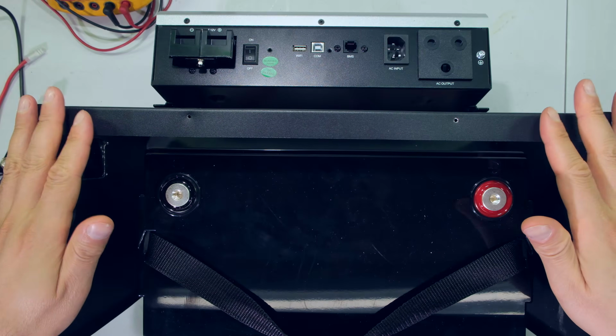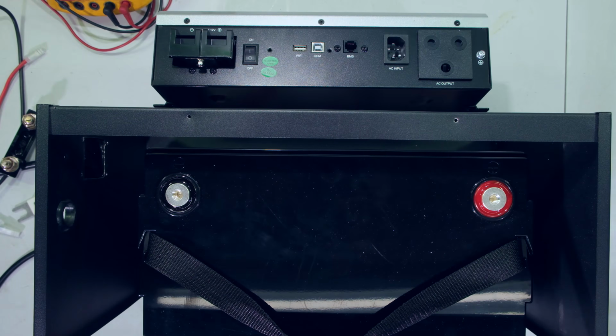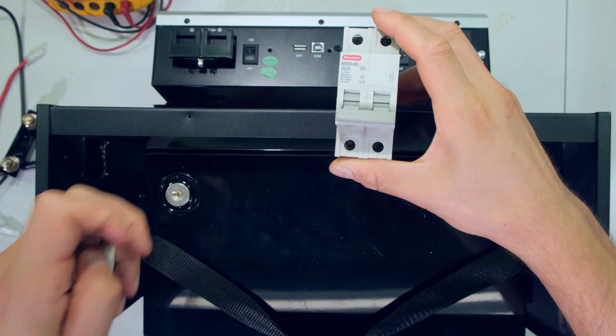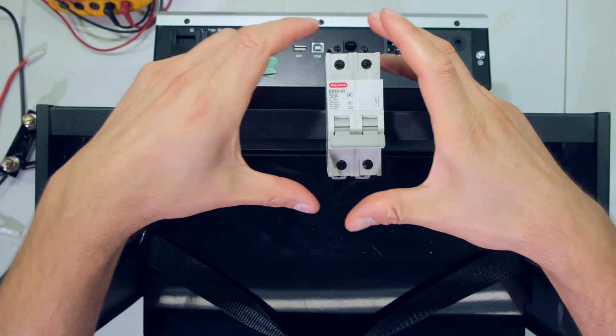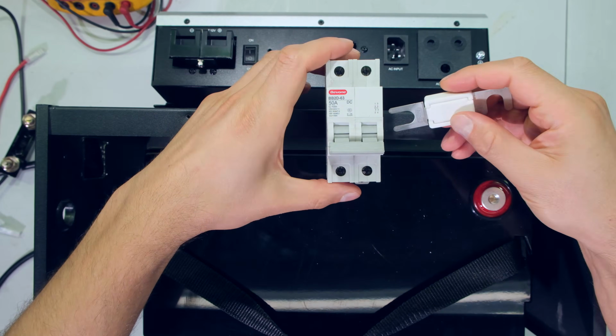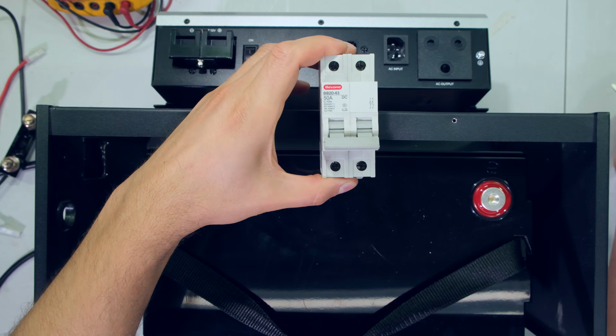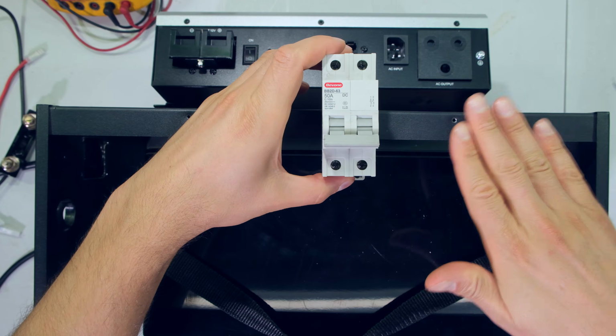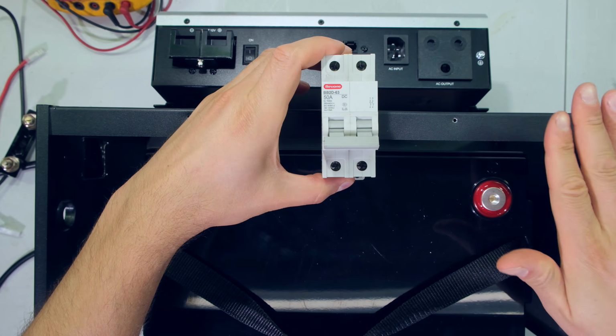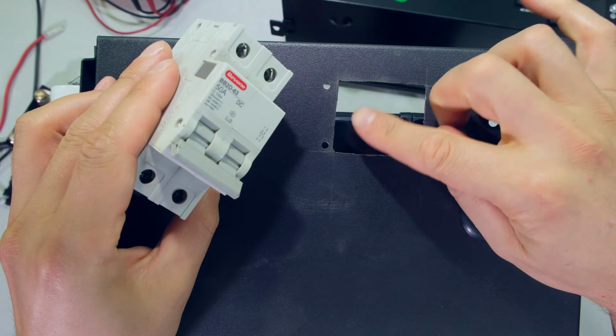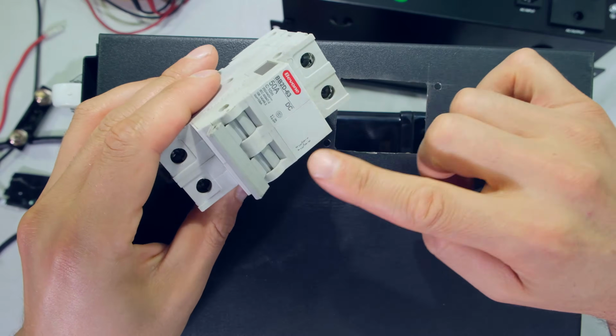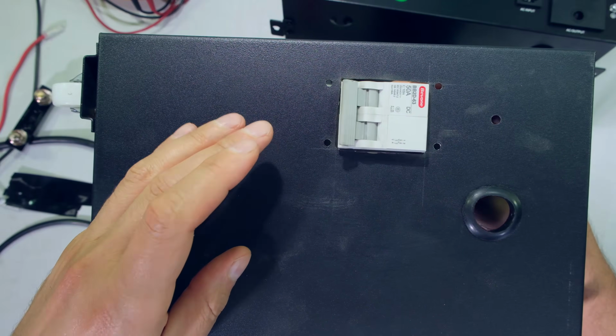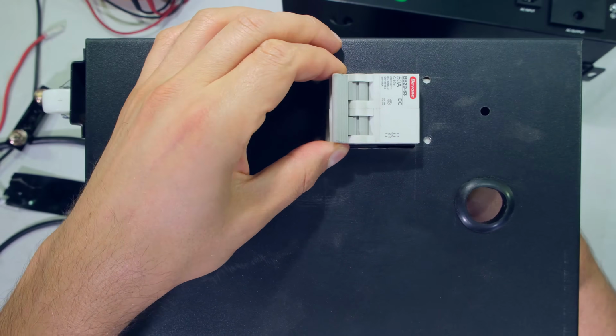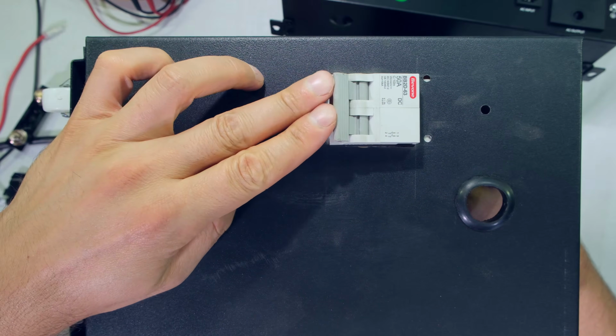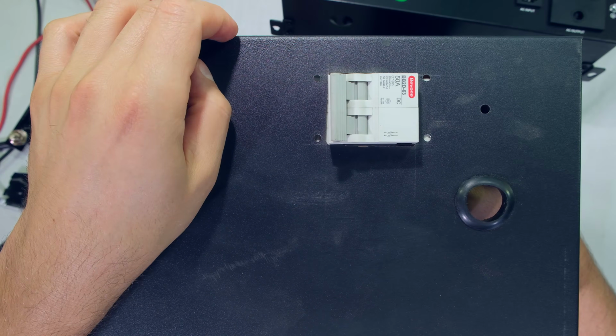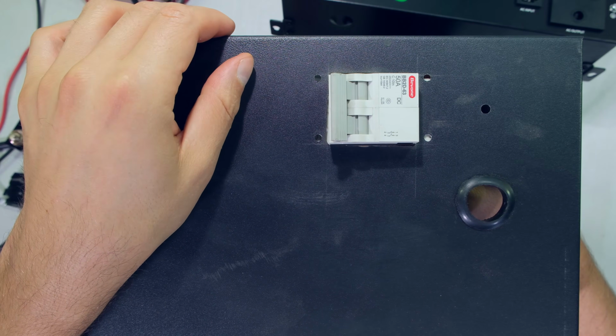All right, so the first step now is to decide if I'm going to use a circuit breaker or a fuse. Now, in this example, I'm going to use the circuit breaker, but I will also just show what to do with the fuse. Now, in order to use the circuit breaker, I'm going to have to cut a hole in this cage or this box that I have here. So on the side here, I've measured the dimensions of the circuit breaker, and then my circuit breaker can fit through there, and I will be screwing it into a frame. So here is my circuit breaker. So all I need to do now is work out the wire lengths.